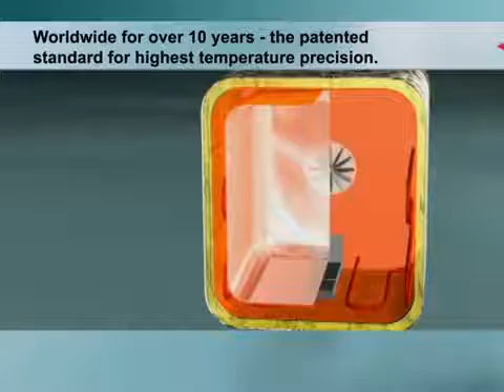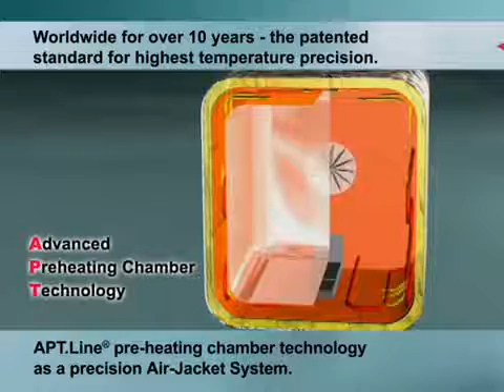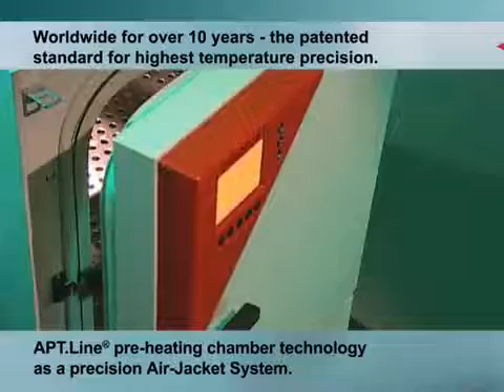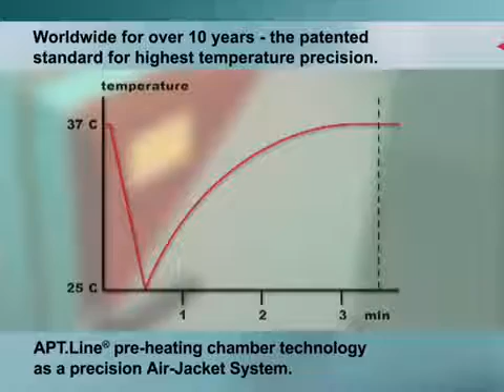With this temperature system, the values relating to precision and dynamic performance far surpass those for existing incubators. One further advantage is the unlimited sterilizability of the whole interior in conformance with standards. APT.line jacket air technology is far superior to the slower responding water jacket system in this respect. The interior temperature of 37 degrees Celsius is restored within only 3 minutes of opening the door. This is clearly faster than other air jacket systems.